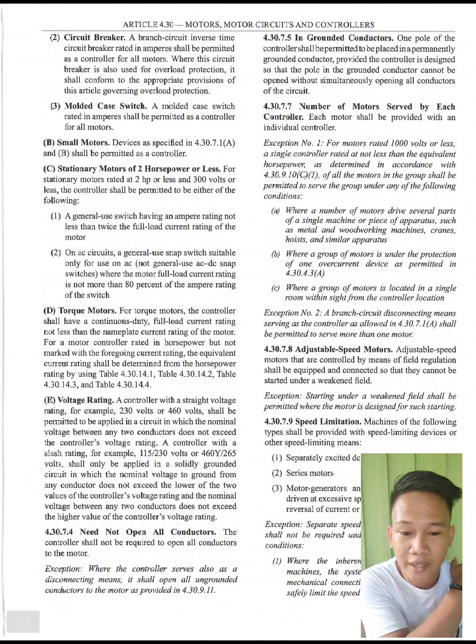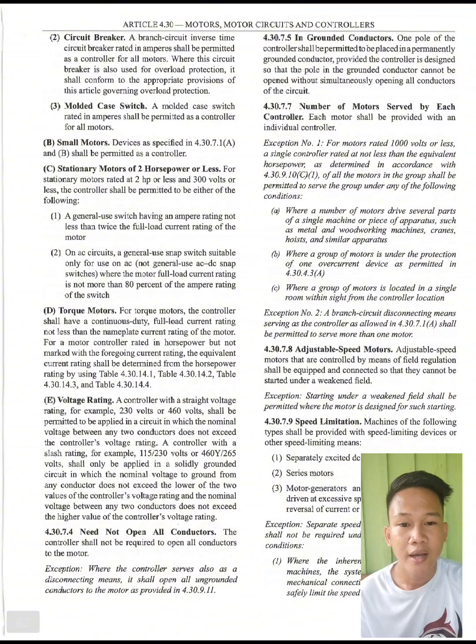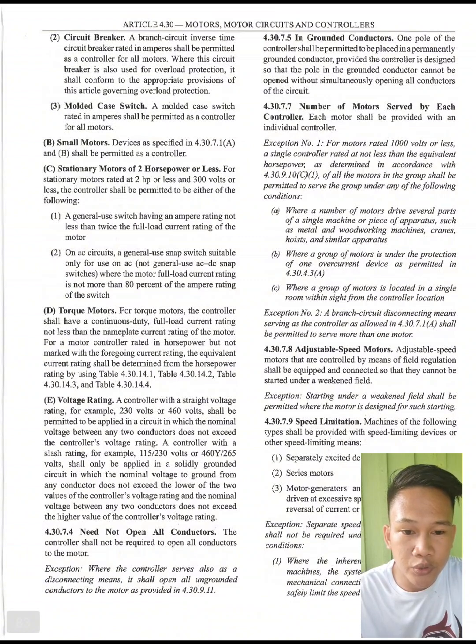First, a general use switch having an ampere rating not less than twice the full load current rating of the motor. Second, an AC general use snap switch suitable only for use on AC, or an AC/DC general use snap switch, where the motor full load current rating is not more than 80% of the ampere rating of the switch. D. Torque motors. For torque motors, the controller shall have a continuous duty full load current rating not less than the nameplate current rating of the motor.